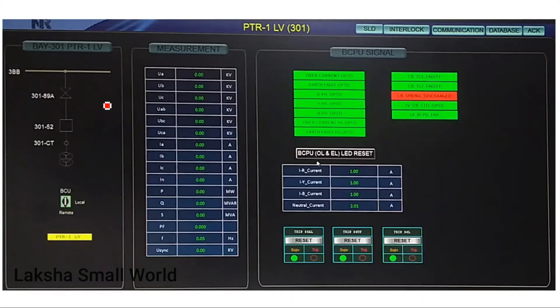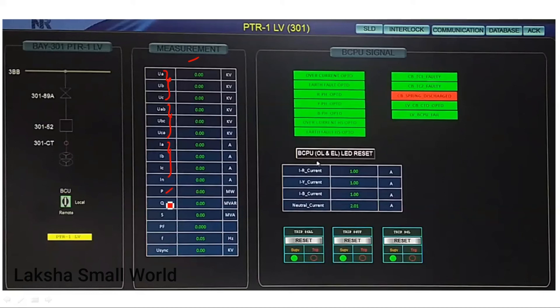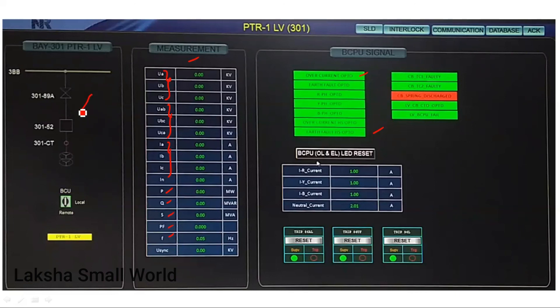Next we will move to the LV side. The LV side measurements include line voltages, line-to-line voltages, line currents, active power, reactive power, and power factor — all on the secondary 33 kV side. Here you will find only the bay control protection unit for overcurrent and earth fault signals. You can also trip the LV side circuit breaker by sitting in the control room and clicking on the parameter. By using automation, we can monitor each and every parameter of the substation and control everything simply from the chair — that is the main advantage of automation.